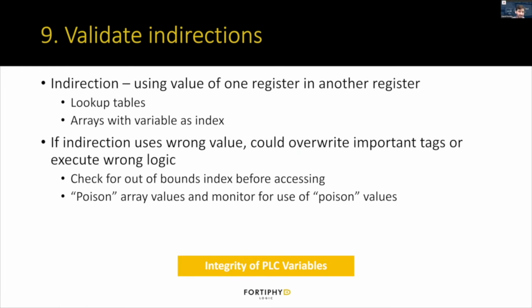Practice number 9 is validating indirections. By indirections, we mean using the value of one register in another register. The most common use case is lookup tables or arrays with a variable as the index. If the indirection uses the wrong value, you could overwrite important tags, execute wrong logic, or try to read out of bounds of the array and cause problems.